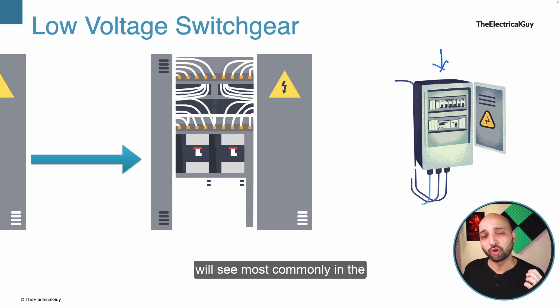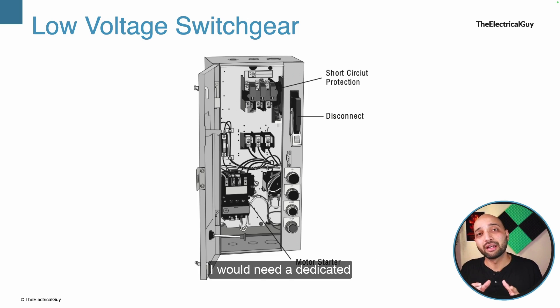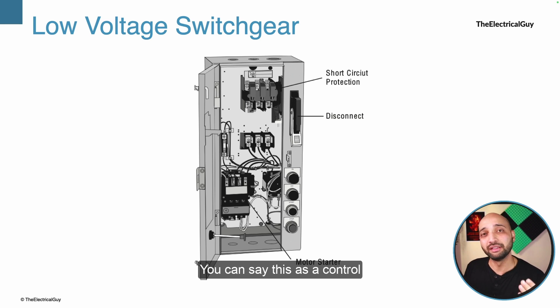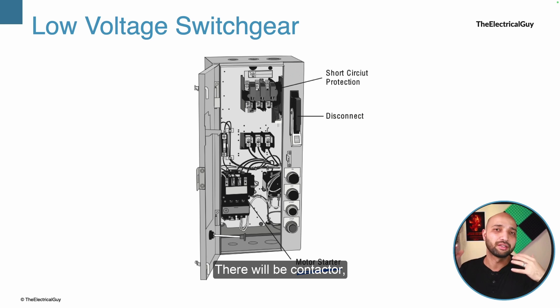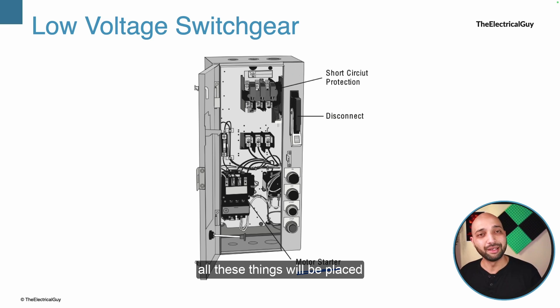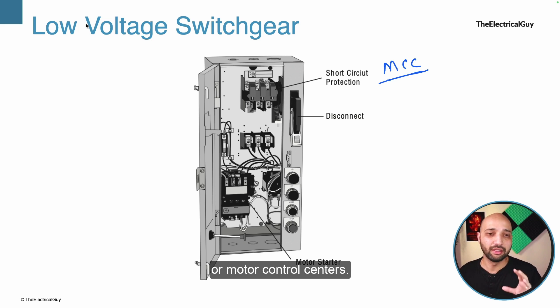Another common element in low voltage switchgear is the Motor Control Center or MCC. In a building there will be motors performing necessary functions, requiring dedicated control. This is sometimes clubbed with the low voltage switchgear, though it is more accurately categorized as control gear. An MCC contains motor starters such as a DOL starter, MCBs to control short circuit currents, contactors, indication systems, and more. All these are placed inside this panel, which is responsible for controlling all the motors in the building.